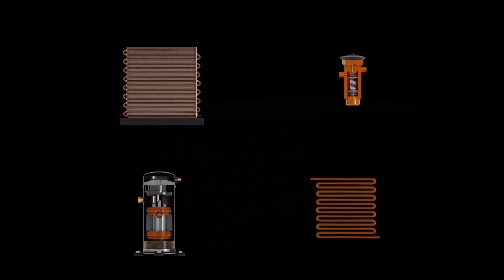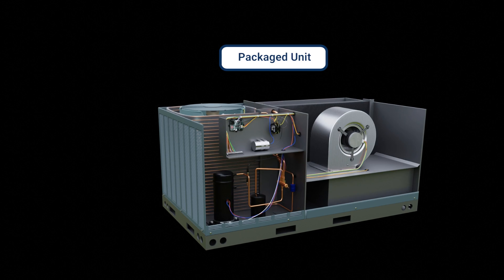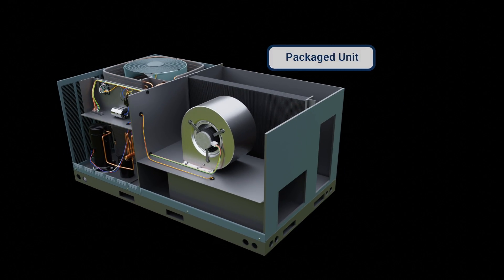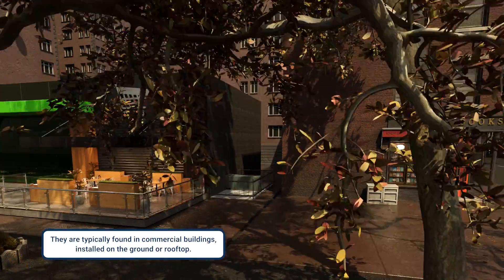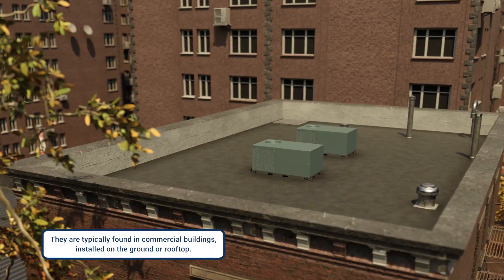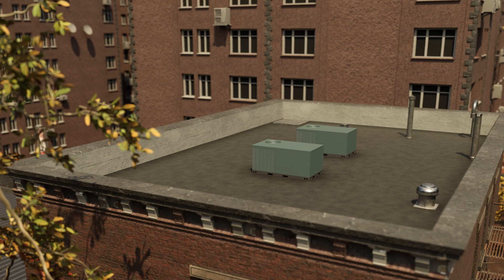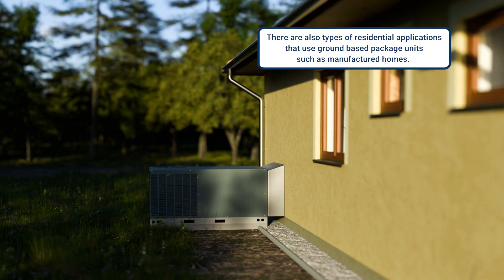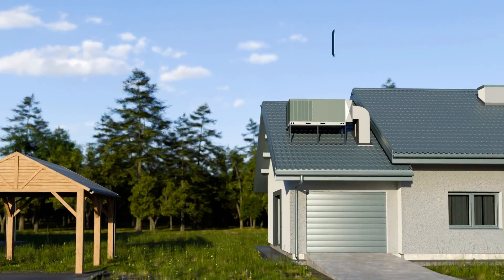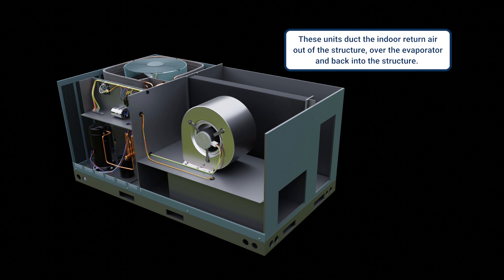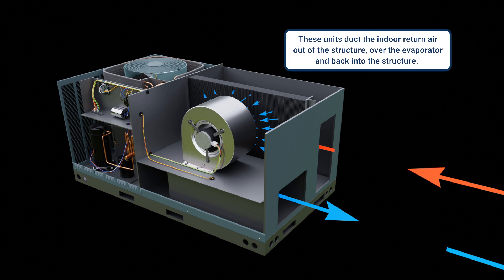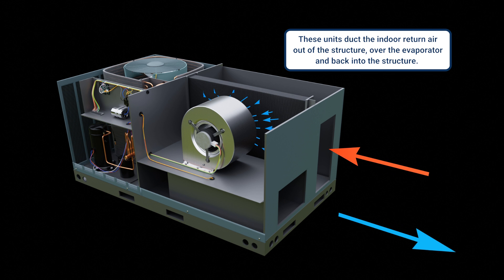A package unit combines the compressor, condenser, and evaporator in a single outdoor unit. They're often found in commercial buildings installed on the ground or on a rooftop. There are also types of residential applications that use ground-based package units, such as manufactured homes, and rooftop residential package units are also common in some western states. These units rely on ducting the indoor return air out of the structure, over the evaporator, and back into the structure.